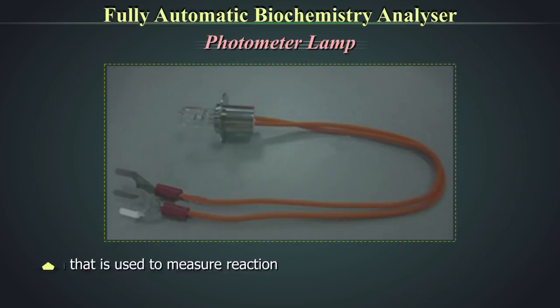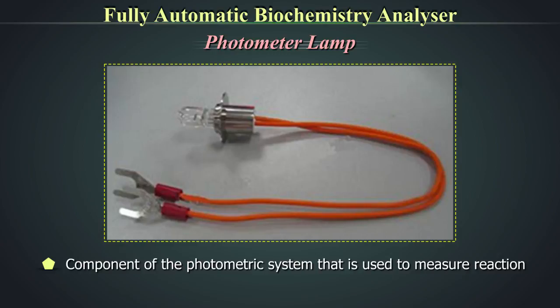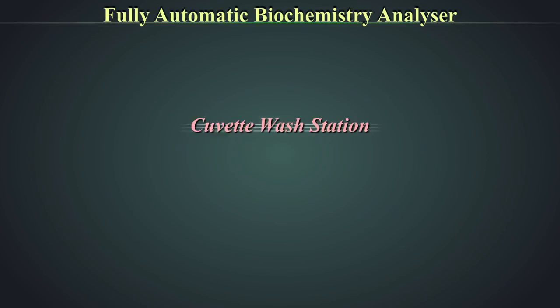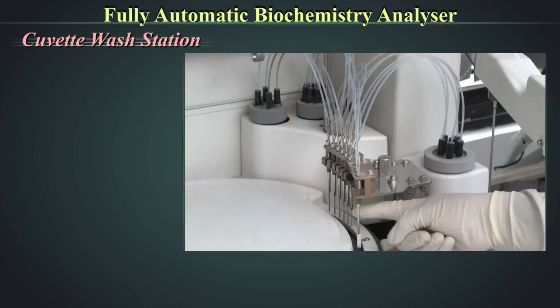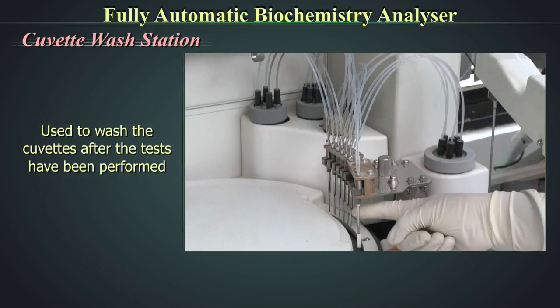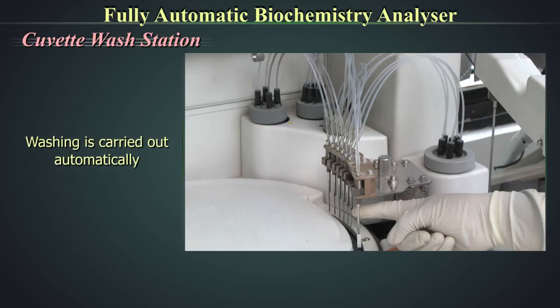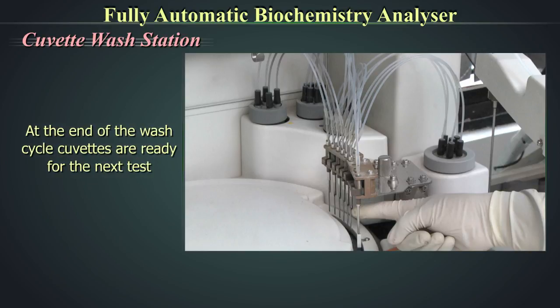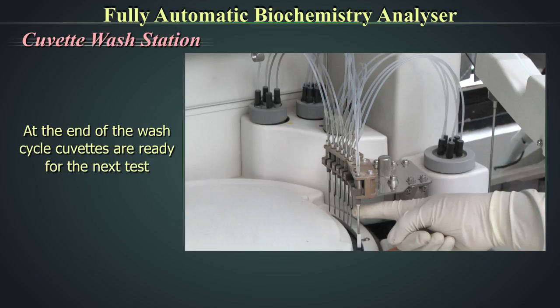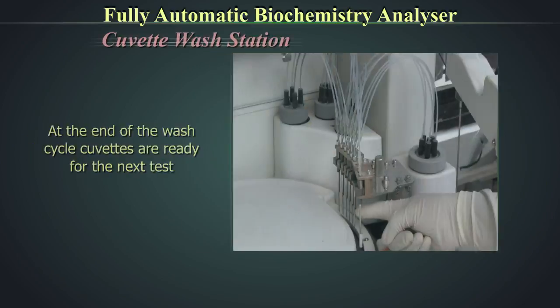The photometer lamp is a component of the photometric system used to measure reactions. The cuvette wash station is used to wash cuvettes after tests have been performed; the washing is carried out automatically. It cleans, rinses, and dries cuvettes after analysis, and at the end of the wash cycle, cuvettes are ready for the next test.